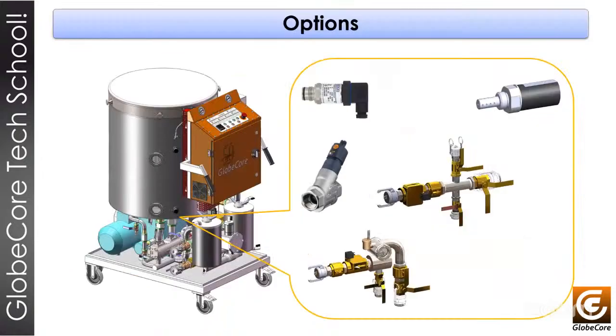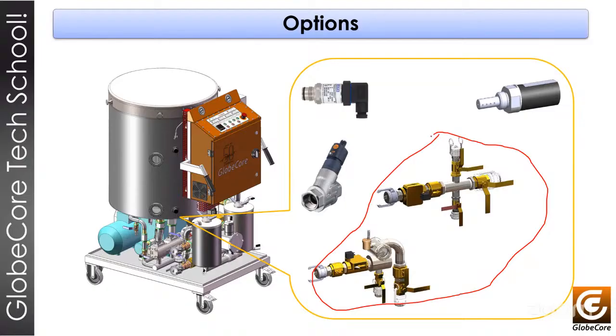We have different options we can add to the machine. We can add a moisture sensor, we can add a particle sensor, we can even add the TSS system, this one. And this system is for working with energized transformers. If we use the machines with the transformer connected to the network, we need a security system that allows us to work with safety. And this is in the standards. We cannot work the machine without this kind of system, and we can add the TSS to all these machines I present today, and that allows you to work with the machine with the transformer energized.